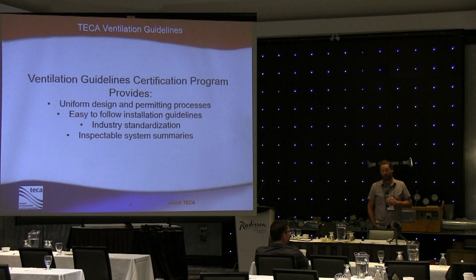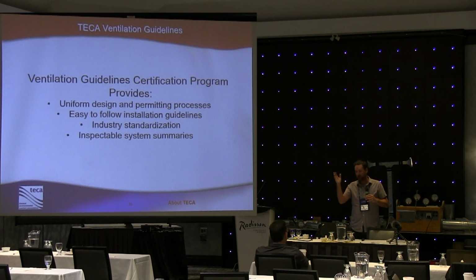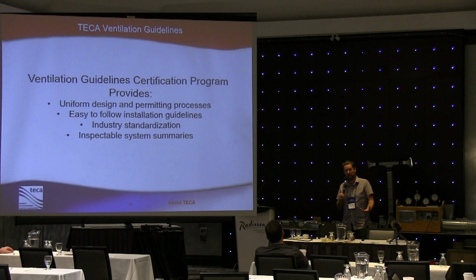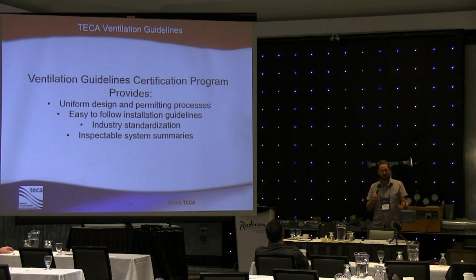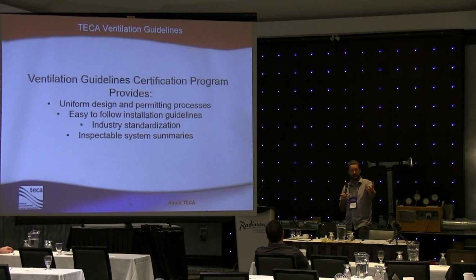Exactly. And that's a challenge too from a contractor's perspective. I've been a contractor for a long time, and quite often either myself or an electrician we work with provides the bath fans, but usually whoever's speccing the kitchen appliances is providing that range hood, right? They're providing that kitchen exhauster. And at the beginning of the project, we need to know what size ductwork to install, and we need to know if we're going to have a problem if we've got naturally aspirated appliances. So we need to be able to identify these things at the beginning. And I can count probably, if I use all my fingers and toes, a lot of times where I've shown up and I've roughed in ductwork for 300 CFM, and I get there and it's 1200 CFM or it's 800 CFM.